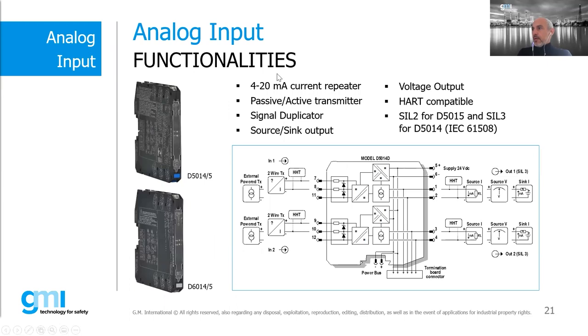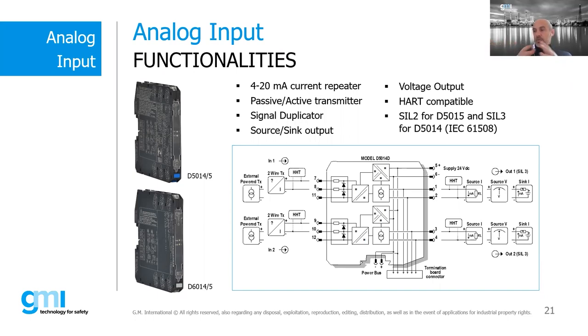Now we look at analog input technology. You can see a schematic of dual-channel modules. There are two types: a blue-label module dedicated to IS (intrinsically safe) technology, and a green-label module for plain isolation in safe applications. Apart from current and power limitations required by the Ex modules, the internal schematic is more or less the same. The module can connect to two-wire sensors (powered by the module) or units with external power, in single or dual channel configurations.